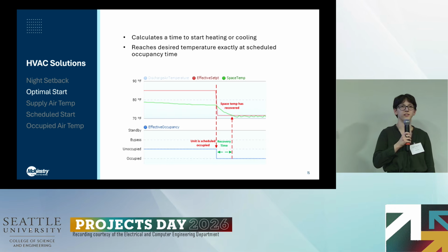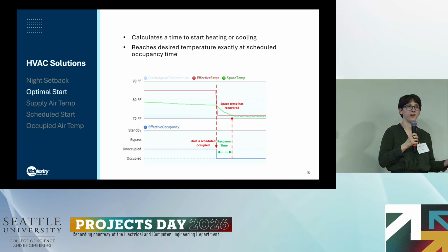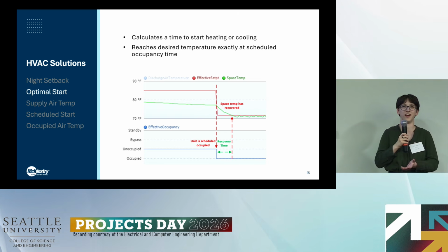Our next optimization strategy is optimal start. This is calculating the time needed for the HVAC systems to get the building back up to our occupied temperatures required. If we started this too early, then it would be a waste of energy, but we still have to have it on time so that the guest comfort with those occupied temperatures is maintained.